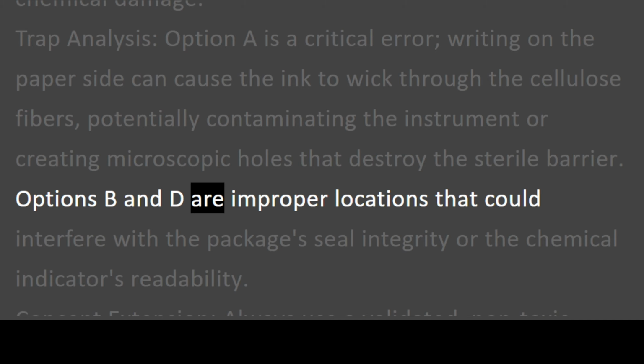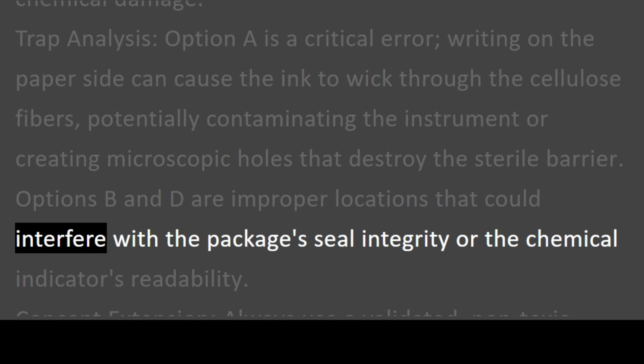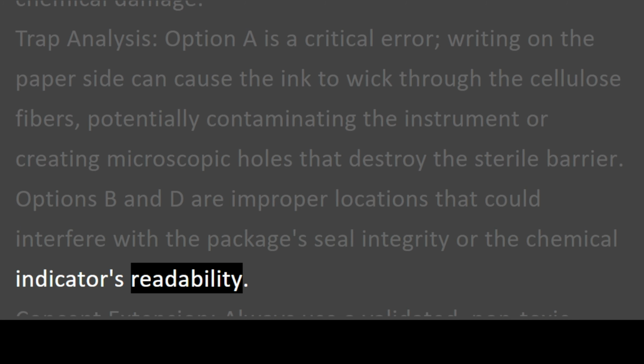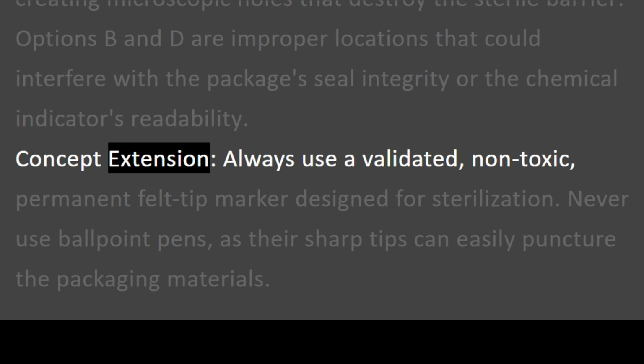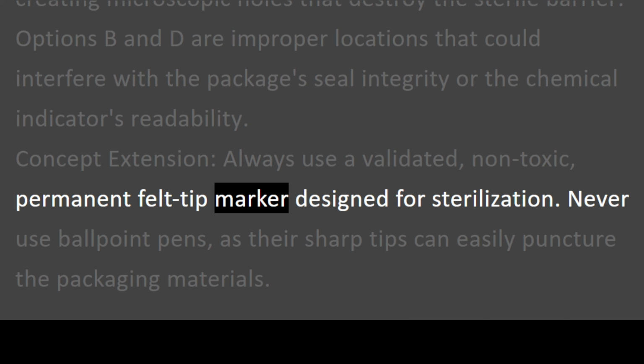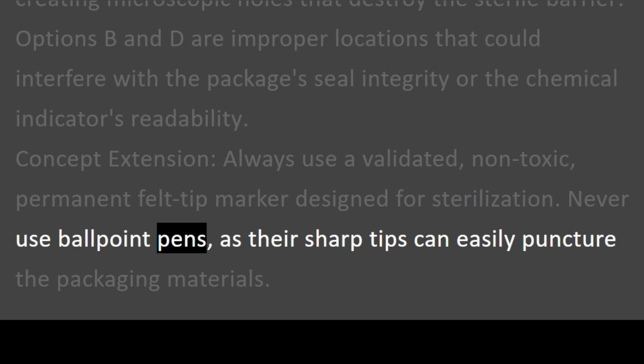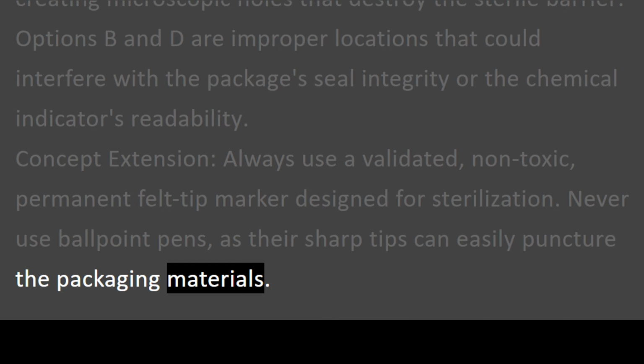Options B and D are improper locations that could interfere with the package's seal integrity or the chemical indicator's readability. Concept extension: always use a validated, non-toxic, permanent felt tip marker designed for sterilization. Never use ballpoint pens, as their sharp tips can easily puncture the packaging materials.